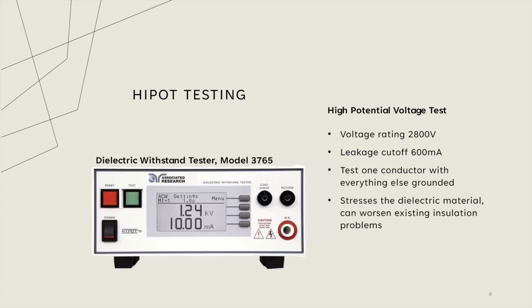So in that preparation, we did a health check of the cable, and we did a high potential voltage test, which is a common manufacturing test for electrical equipment. We used this dielectric withstand tester, which stresses the dielectric material, that insulation on the conductors, at the operating voltage of the manufacturer's voltage of the cable. So that's 2,800 volts for this cable. We short all of the other conductive material together, and you're measuring for a leakage current from that conductor to the other conductors. If there's any leakage, the tester will shut itself down, and if there's any problem with the dielectric material, this test can worsen that problem.